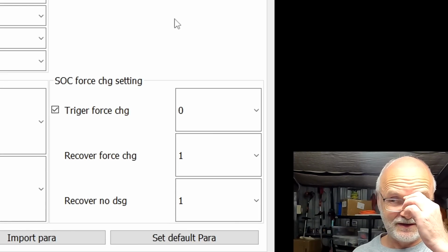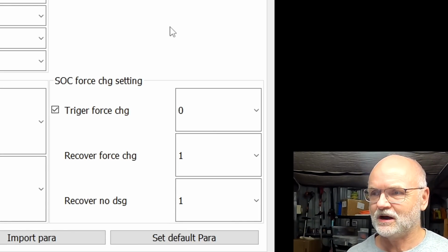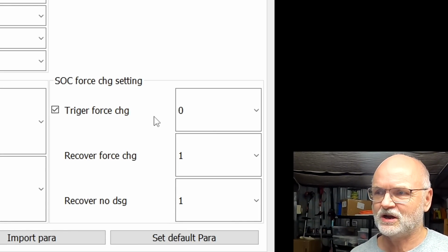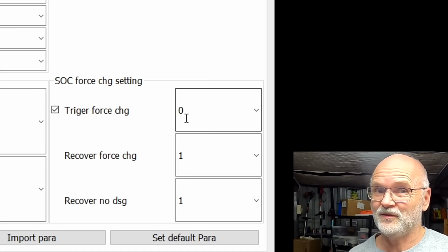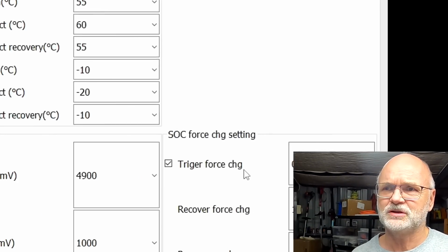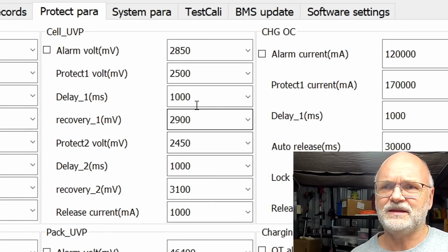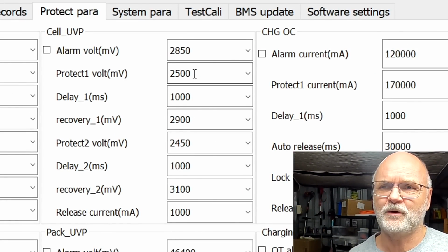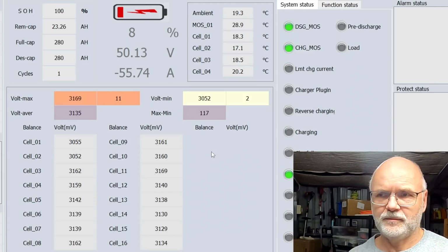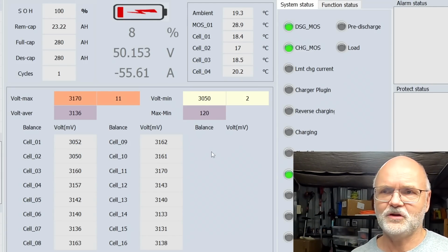I did some changes in the settings during the discharge. I set the trigger force charge here to 0 - I think this is when the BMS usually turns off. Charging or discharging disconnect at 0%, so we really fully discharge. I also set the cell under voltage protection from 2.7 to 2.5. We don't want to forget that. Apart from that, it's working great - best battery ever, who would have thought?